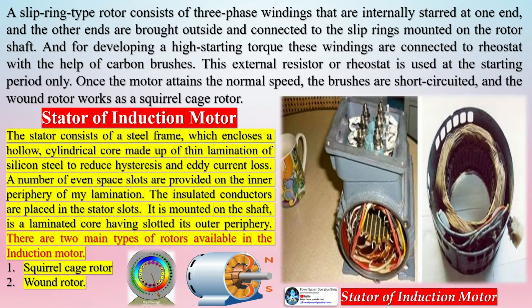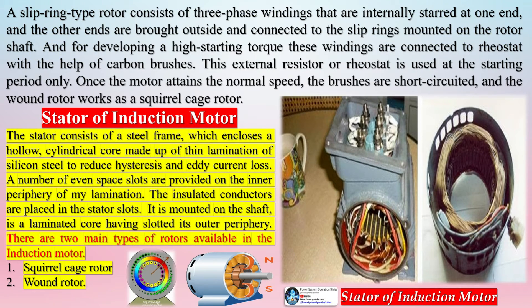For developing high starting torque, these windings are connected to a rheostat with the help of carbon brushes. This external resistor or rheostat is used at the starting period only. Once the motor reaches normal speed, the brushes are short-circuited and the wound rotor works as a squirrel cage rotor.